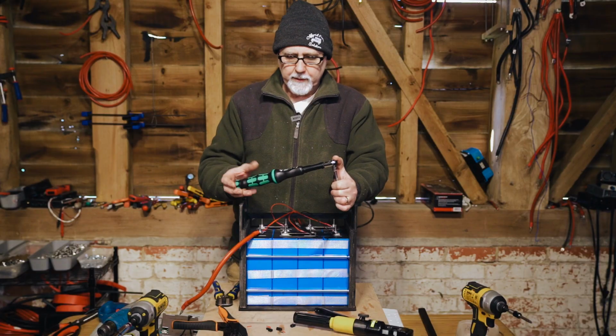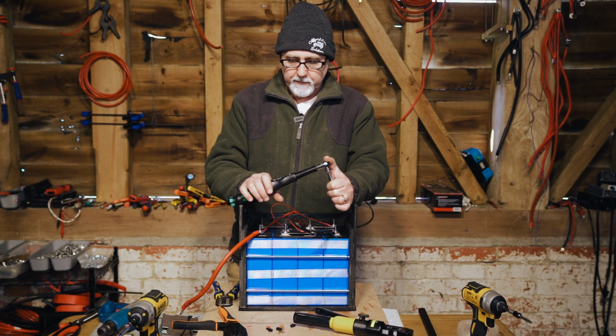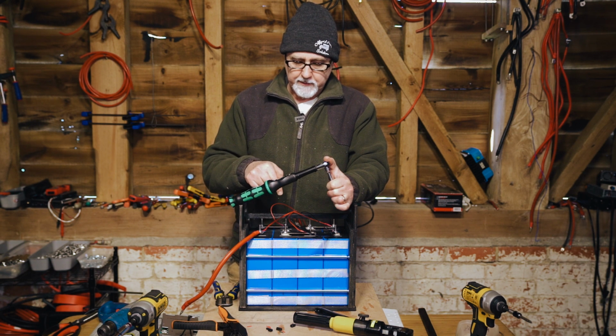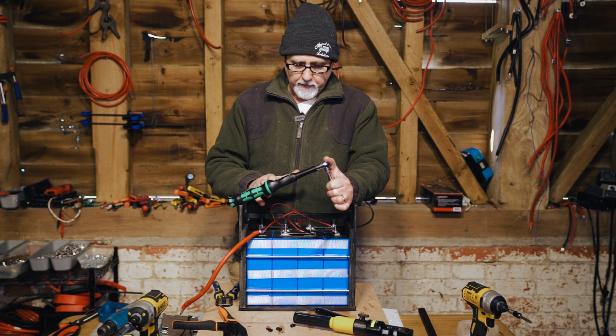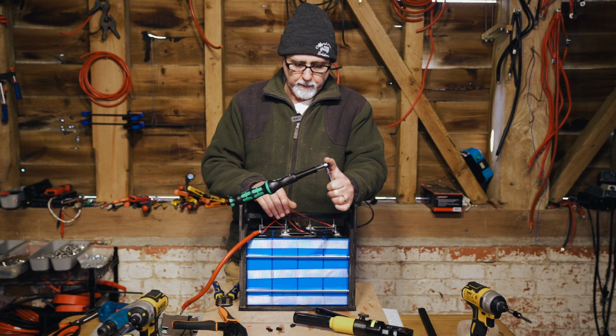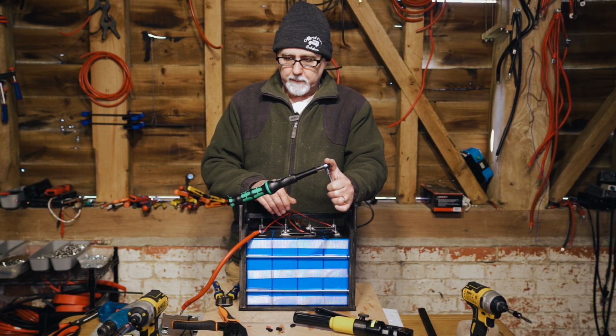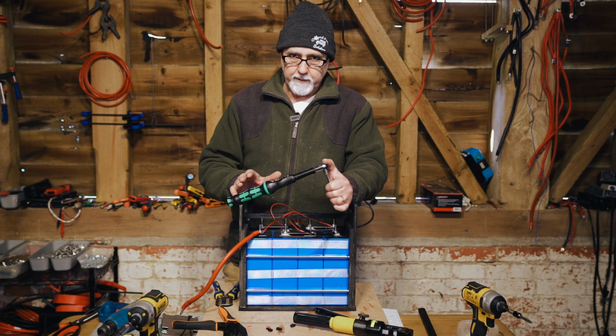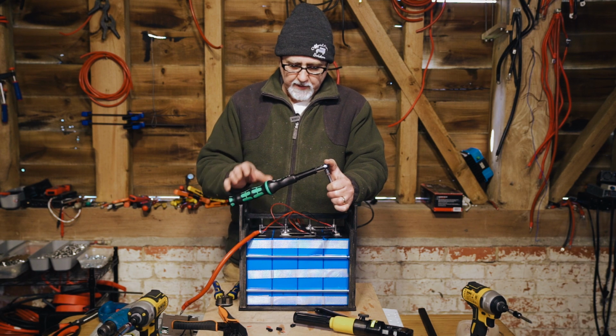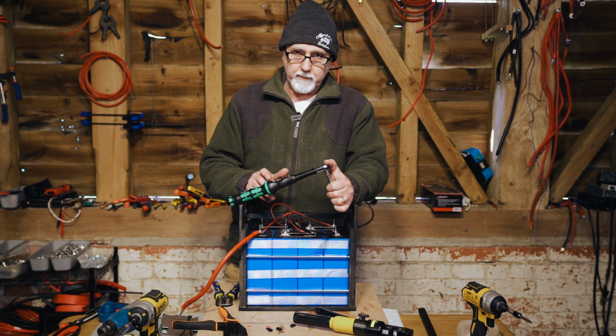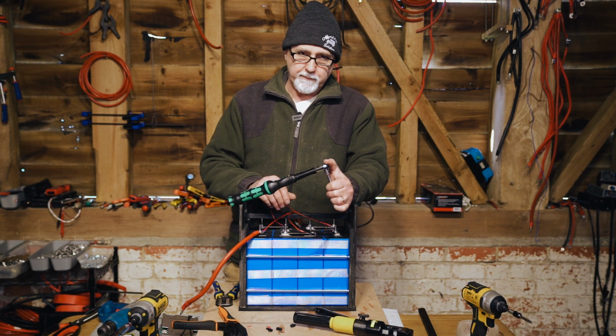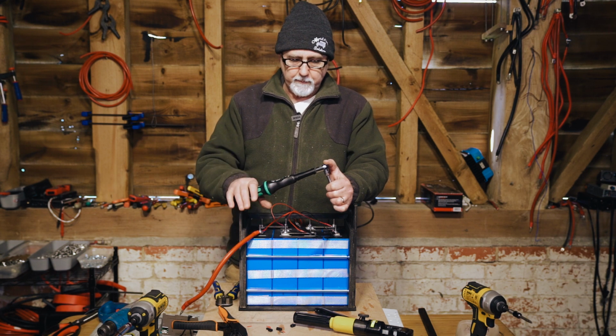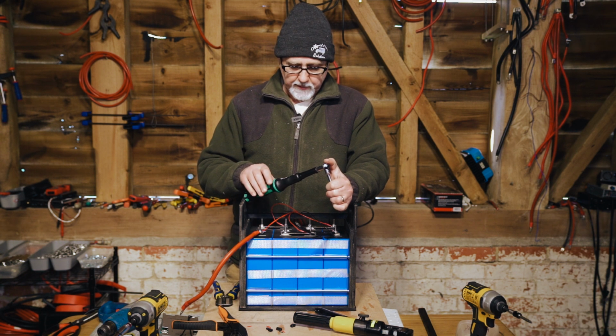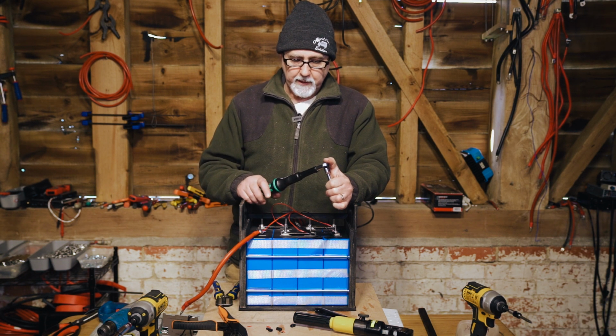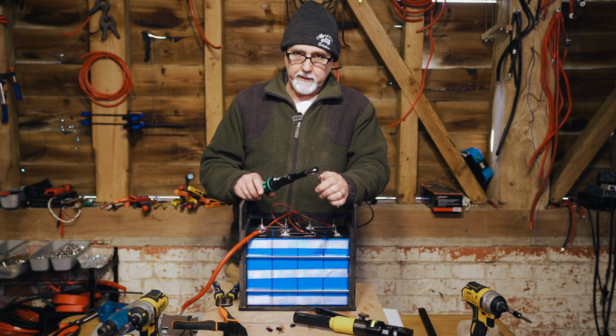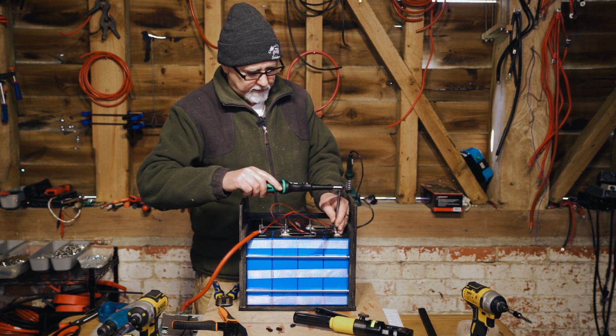So let's torque these down. It's a good idea to torque these to the correct torque appropriate for your cells. Most of the cells we sell range about 8 to 10 Newton meters, and as a rule of thumb we torque them to about 9 Newton meters. In a very high current situation, we'll torque it down to 10 Newton meters. We've tested the studs on our cells to about 22 Newton meters, which is when they actually shear. We think around 15 Newton meters is when structural damage occurs in the cell from torquing. So torquing these to 8 to 10 Newton meters is absolutely fine, and we've done some stress tests, and there's not really anything in it in terms of heat buildup. So let's get these all down to the right torque.